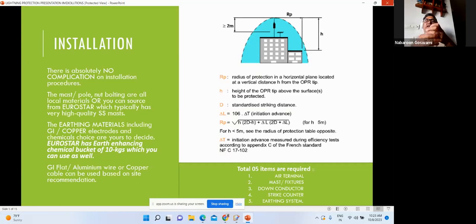You need a mast or pole on which, with nut and bolting, you put up the lightning protection system, and then a copper cable, or a GI strip, or even today aluminum down conductors of 8mm. One of the groups I'm associated with, called the Eurostar group, uses aluminum down conductors along with the air terminals.